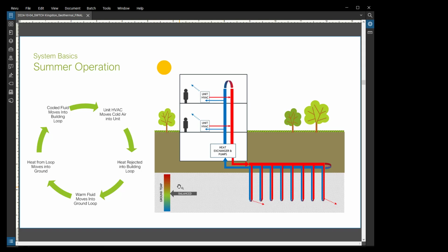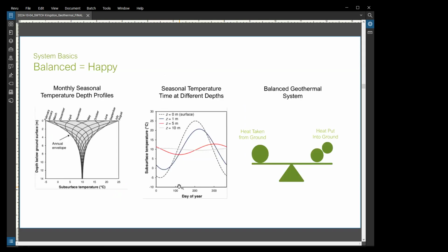And the idea is that over the course of a year, you end up with a nice balanced system. So you take the heat out and you put it back in, and you take the heat out and you put it back in. And that would be a perfect balanced system. But in reality, the systems are never 100% perfectly balanced, mainly because if you think about where we live, we spend a lot more time heating than we do cooling our spaces. And so just intuitively, you think, well, we're heating more, so over the course of the year we're going to be taking more heat from the ground. So how do we mitigate against that? And how do we make sure that we're still balanced at the end of every year?